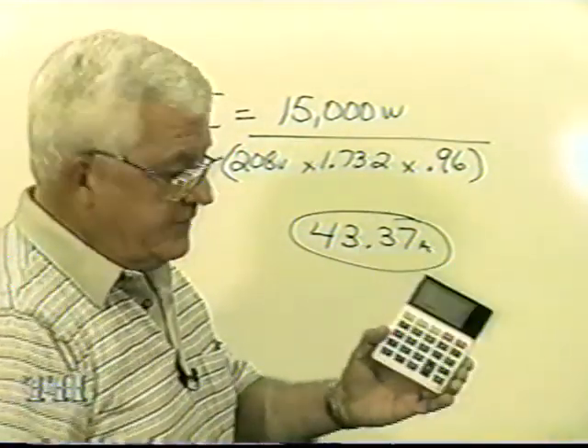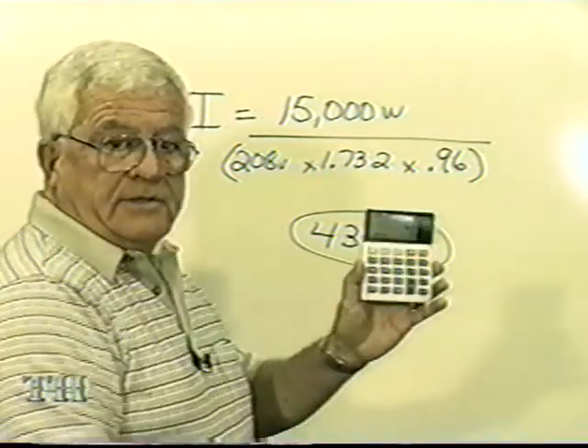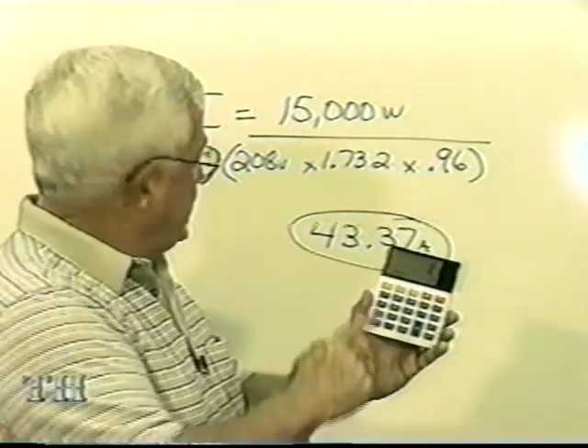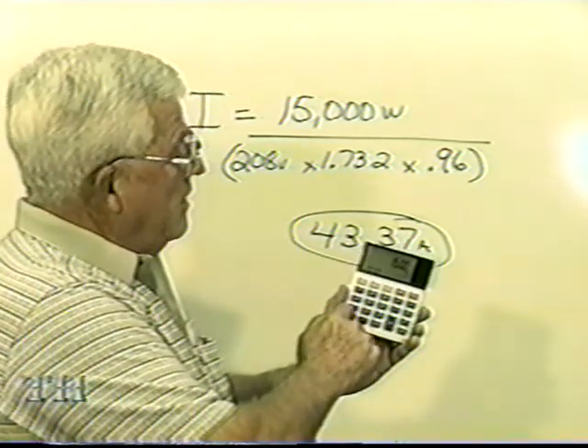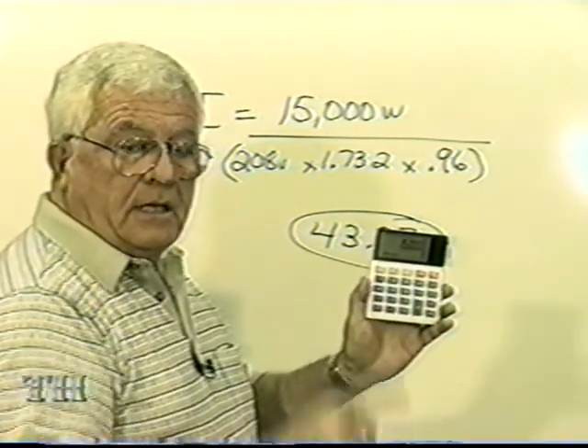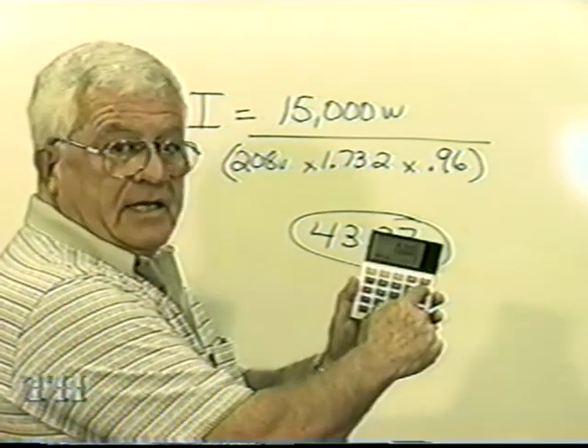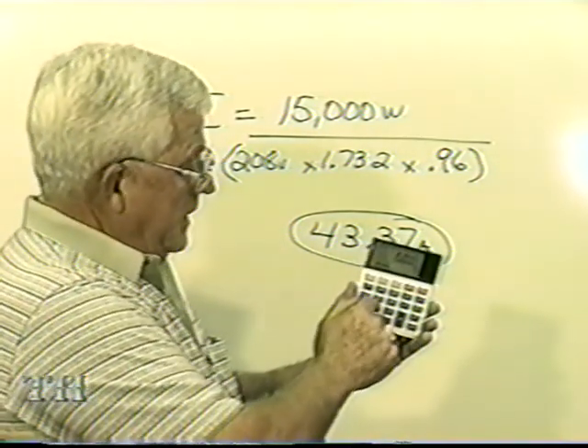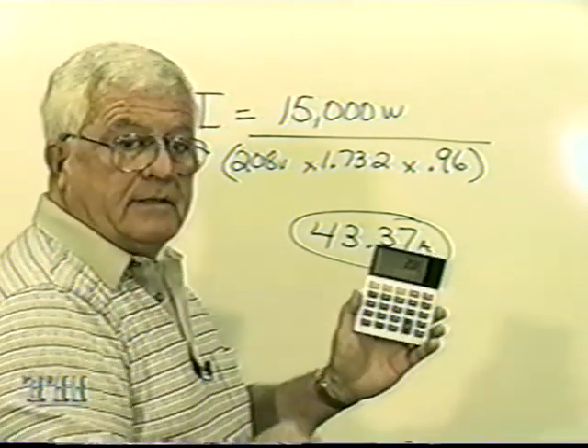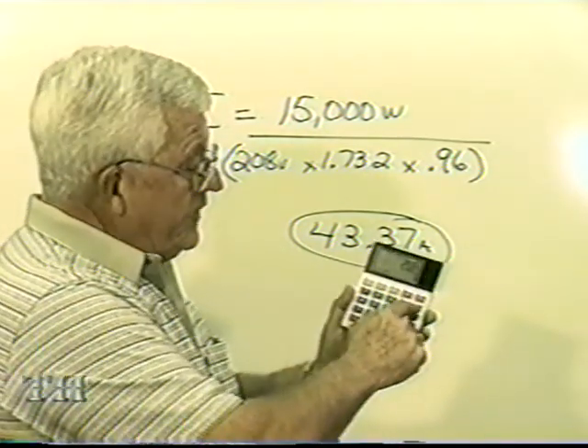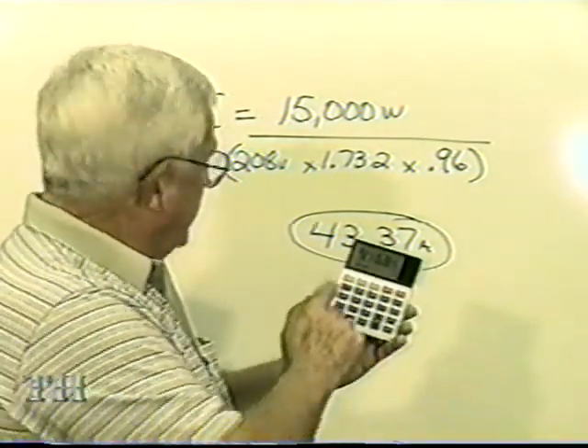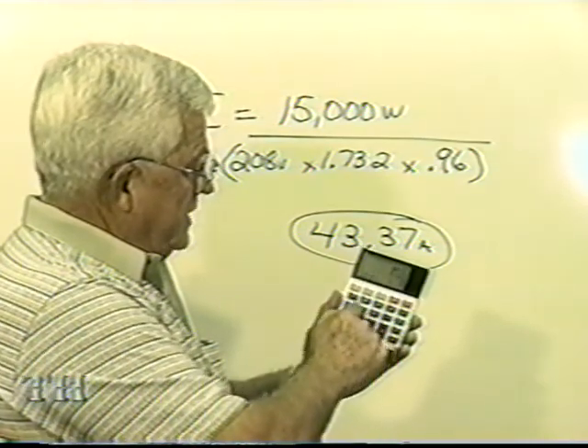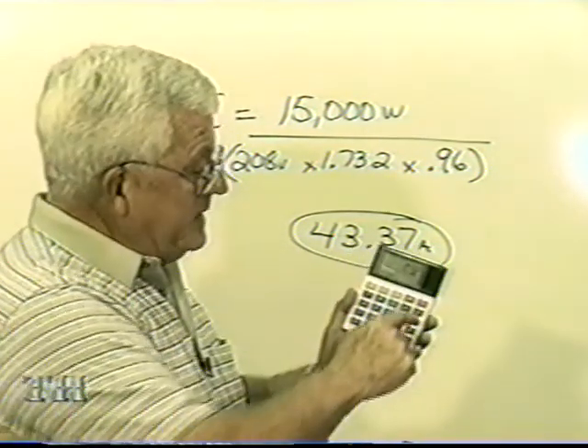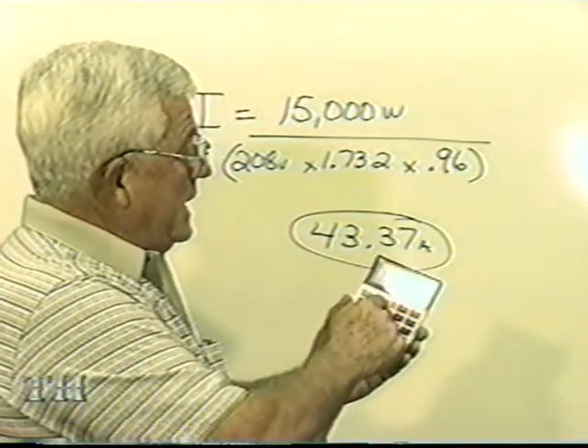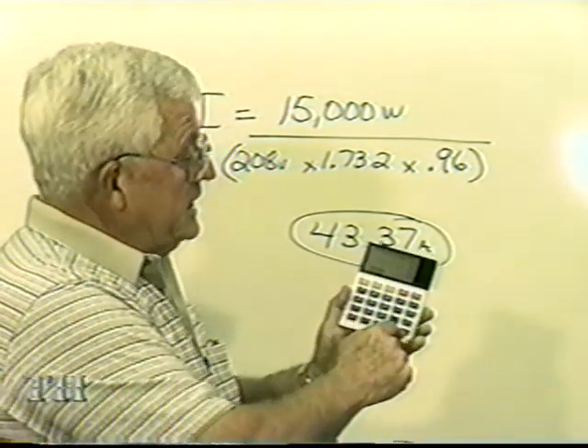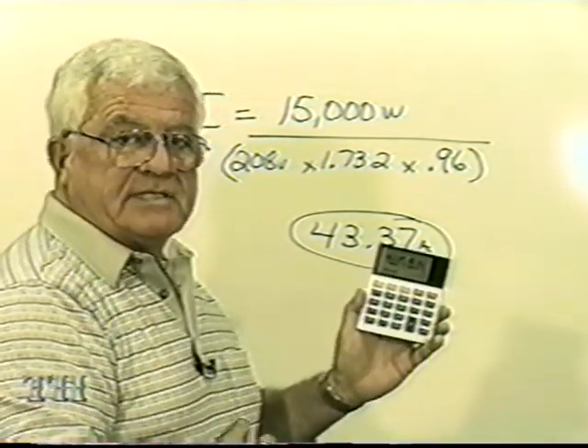I've done this on other videos, but I'll do it again. Take your calculator, put it on zero. Now press 15,000. Now hit the divide button. Press 208. Now here comes the important thing: hit the divide button, press 1.732, hit the divide button, press 0.96, press equals: 43.37.